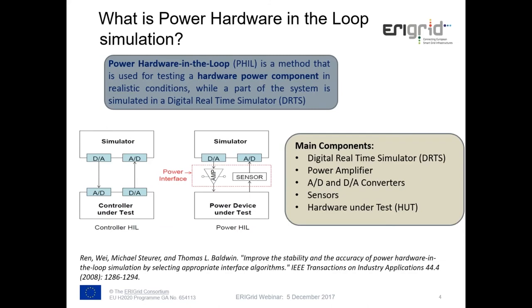In general, what is hardware-in-the-loop? Basically, it is a combination of simulation and hardware. As we can see in this figure, we have a simulation of a power system, but we also connect some hardware components externally. We can have power components — for example, PV inverters or whole microgrids — but we can also have control components, such as centralized controllers for optimizations, relays, or controllers of inverters.